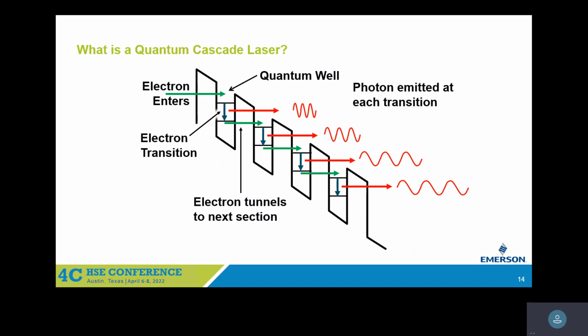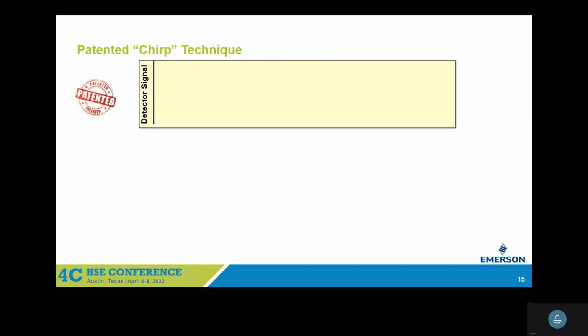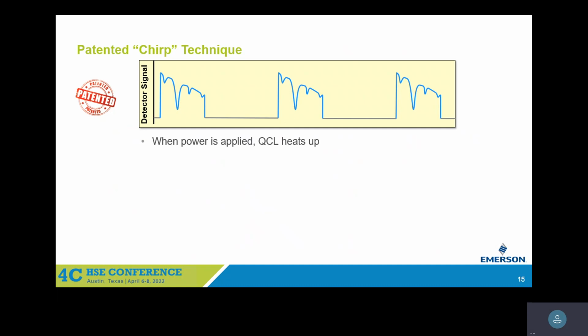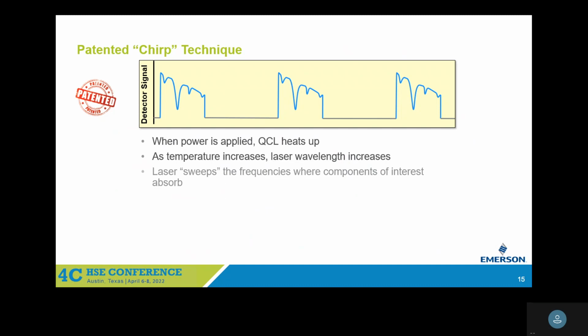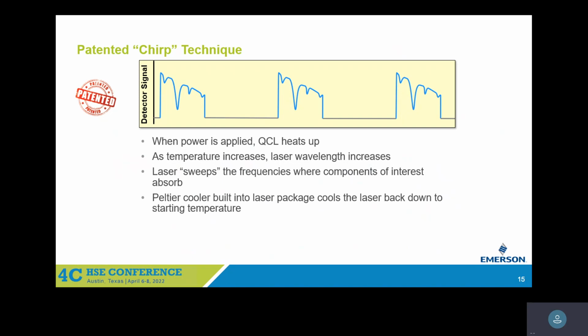What happens is that the wavelength increases slightly as the laser heats up a little bit. It's still very, very narrow, very specific, but we get a little bit of width to the window that we're looking at, so we can gather more information. What we call this is chirping. So we apply the power, electron current goes into the well, and the laser wavelength sweeps across frequencies. So these are the absorption peaks you see right here. It sweeps that whole package down very quickly. Now, if you remember, there's no thermal mass here at all. Very, very quickly.